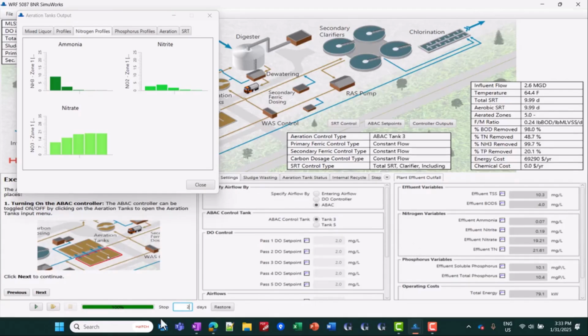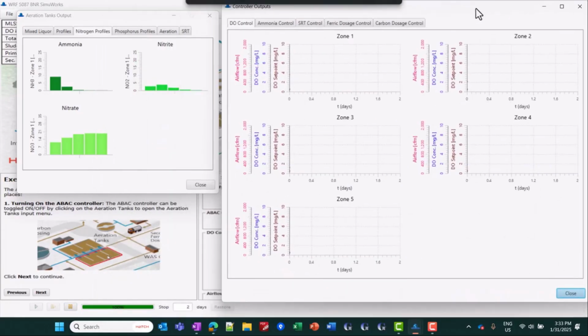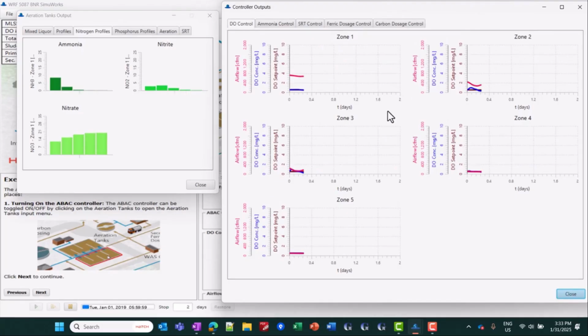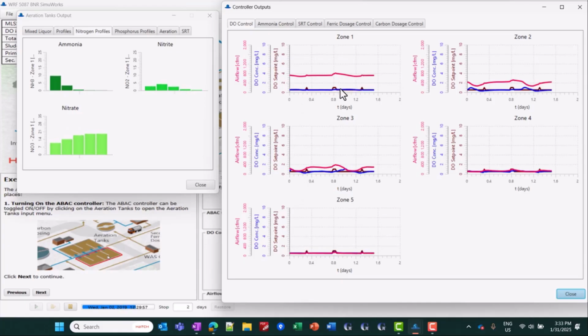So now let's run that dynamic simulation, and I'm going to open that controller output back up again. We can see here that our DO set points are different than previous. Instead of being at 2 across the board, they're now down at 0.5, and occasionally they bump up to 1 when there's a really high loading.